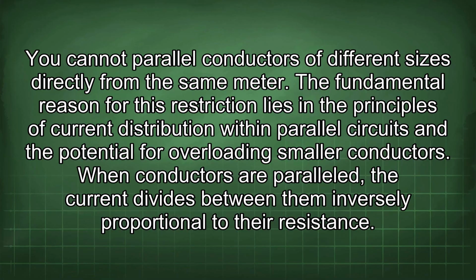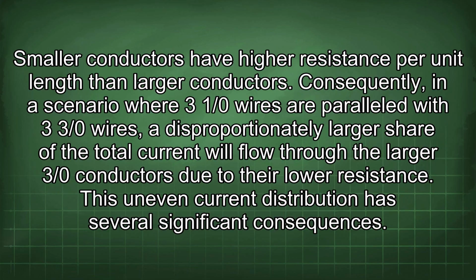You cannot parallel conductors of different sizes directly from the same meter. The fundamental reason for this restriction lies in the principles of current distribution within parallel circuits and the potential for overloading smaller conductors. When conductors are parallel, the current divides between them inversely proportional to their resistance. Smaller conductors have higher resistance per unit length than larger conductors.